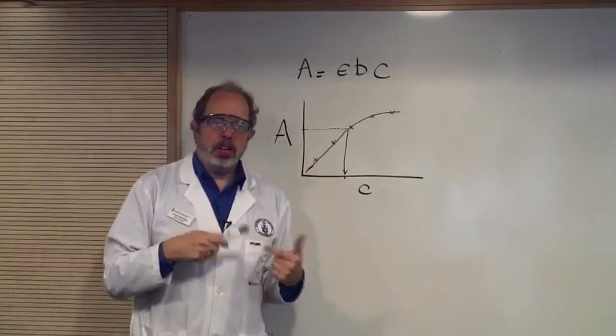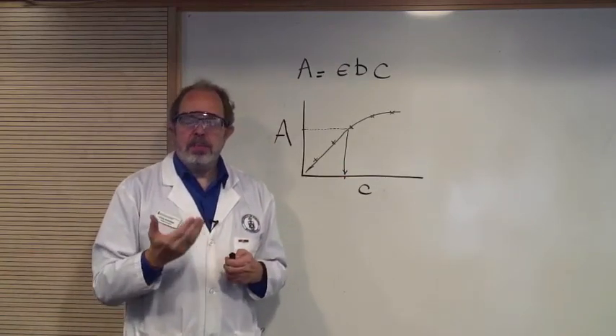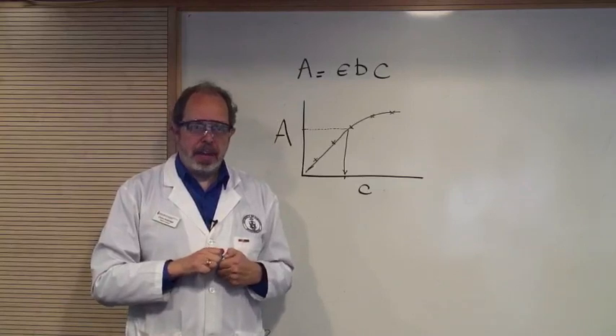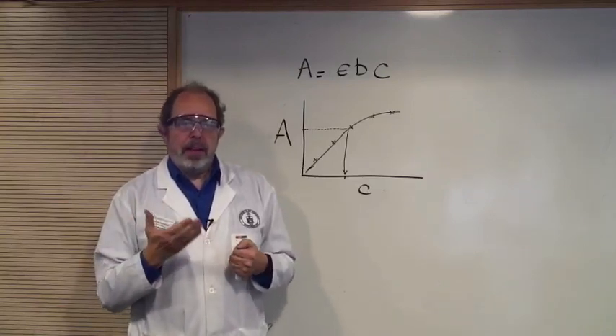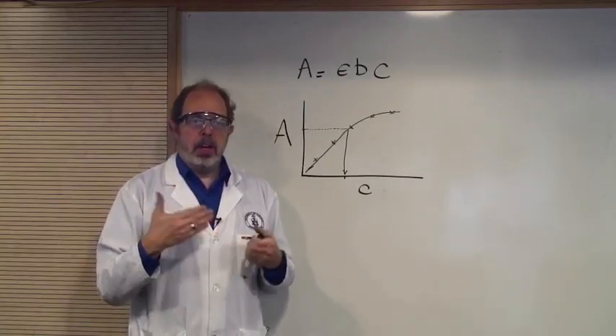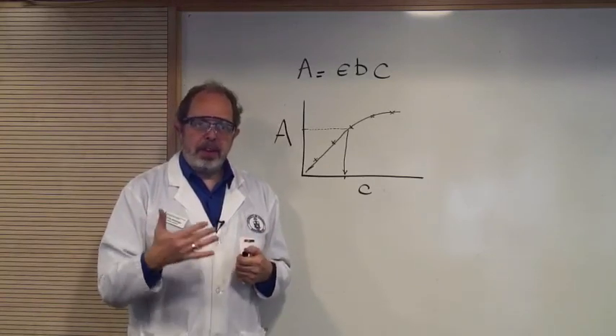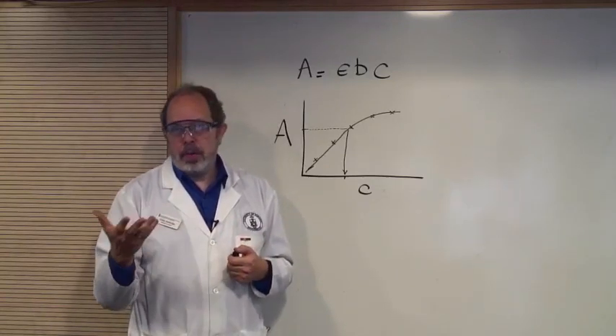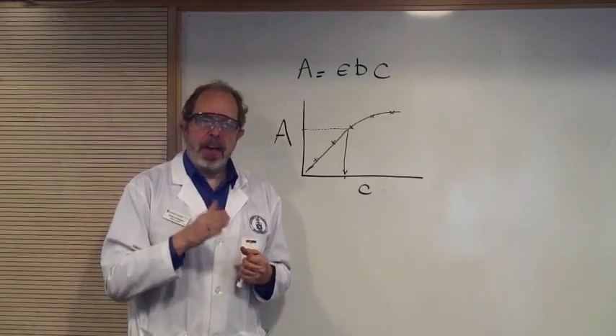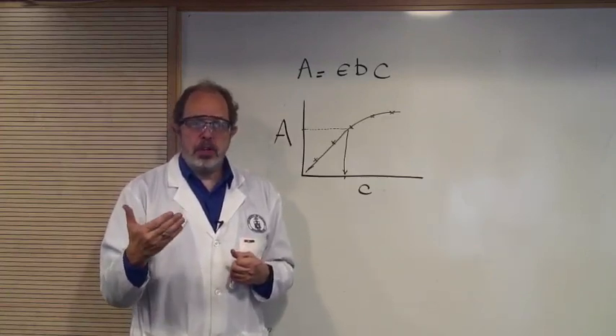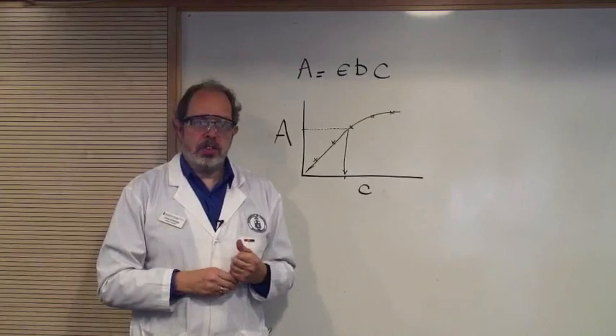All of this holds at a constant wavelength. Because the absorbance varies as a function of lambda, the wavelength, the measurement should be made at the optimum wavelength. And usually, that's the wavelength where absorbance is highest. We call that lambda max. Because at that wavelength, the absorbance is going to be most sensitive to a change in concentration.